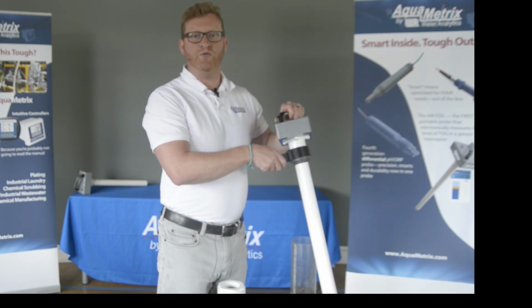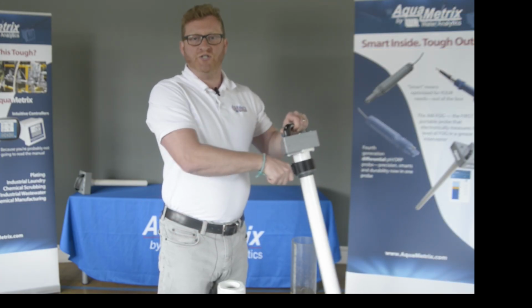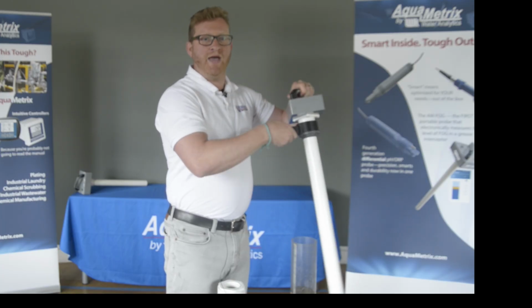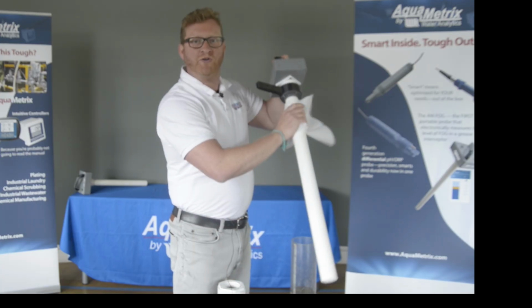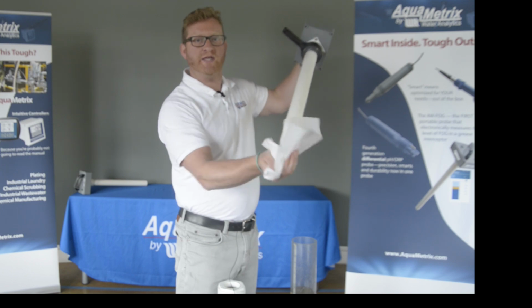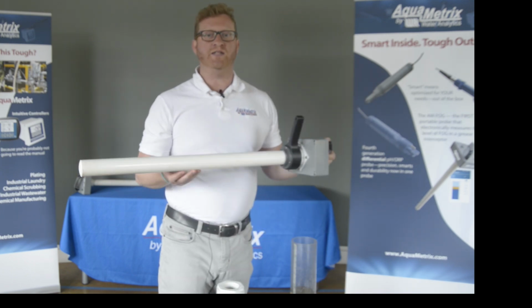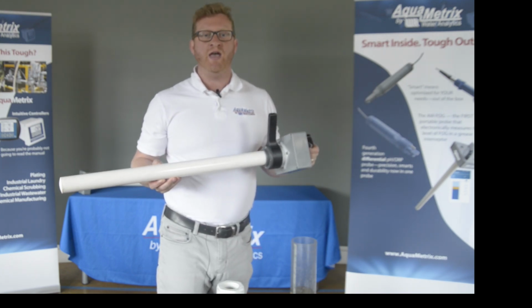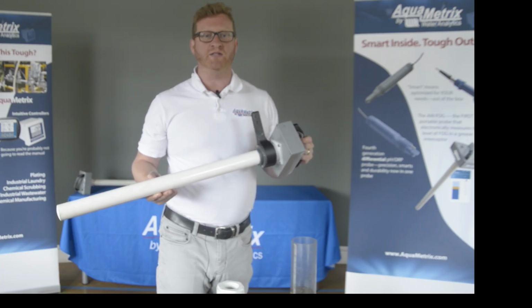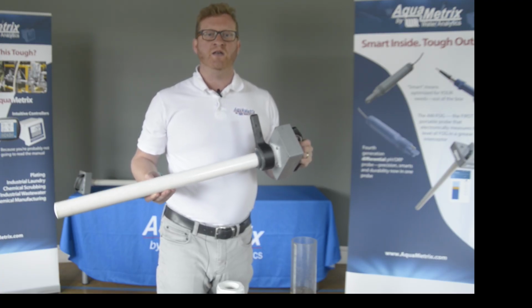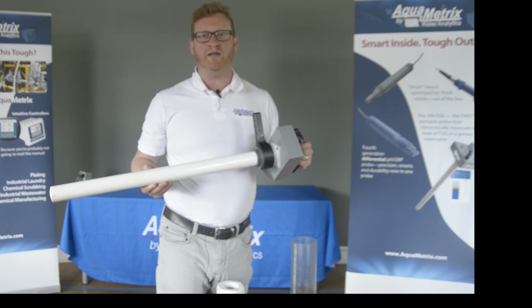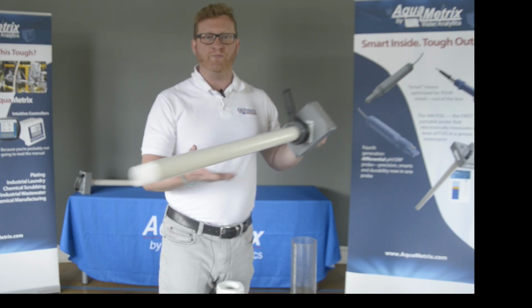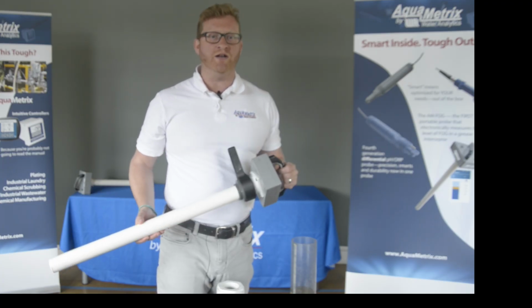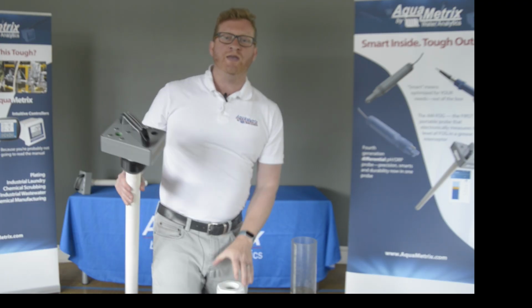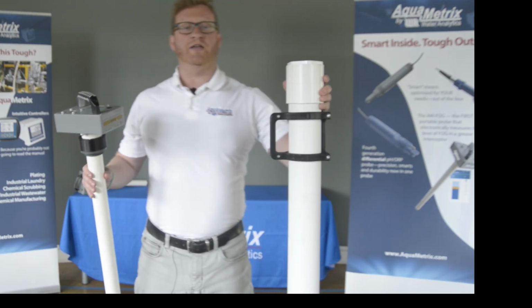The mess of the core sampler is gone, but the probe still has a coating of grease when you remove it. That's where the squeegee comes in. Just slide it down and up again, and one wet wipe after the wiper will make your probe squeaky clean. The AM-Fog sensor needs calibrating about once every month. This takes about 4 minutes, and all you need is to immerse it in water and again in air. Air is easy, but where are you going to find a container that is deep enough and filled with water? Easy, the carrying case.